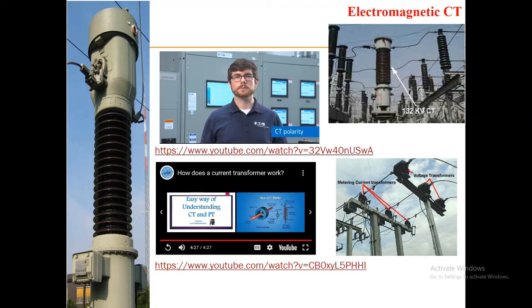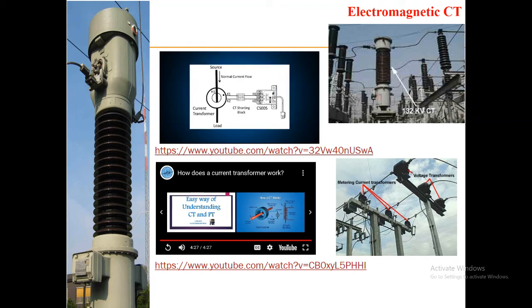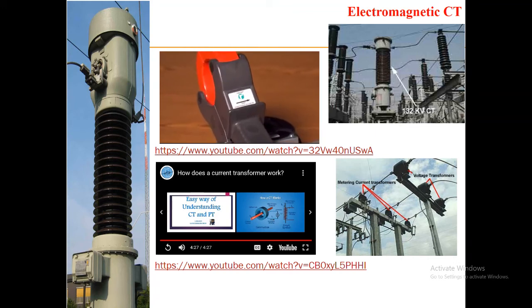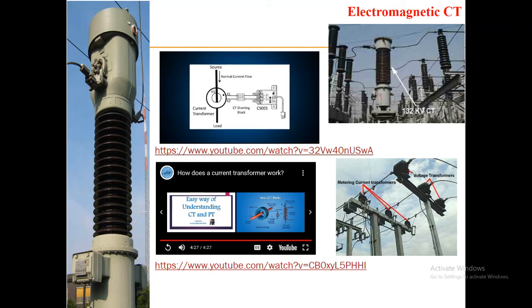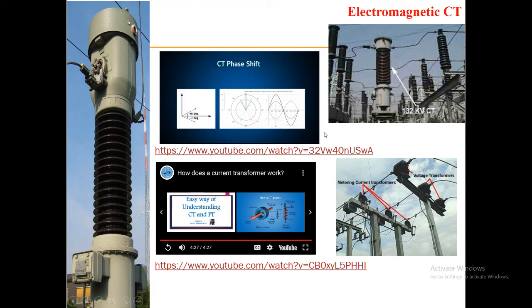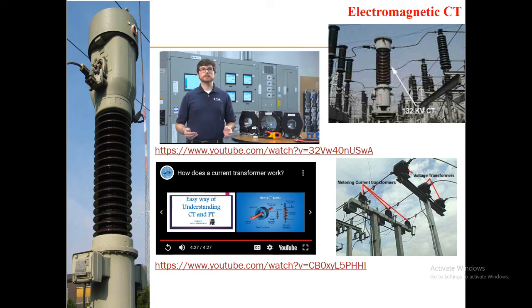In addition to CT saturation, the maximum frequency range that a CT can measure is typically 3 to 5 kilohertz. For most applications, this is okay since the harmonics on the power system are typically within this range. However, for high frequency applications like transients in the hundreds of kilohertz or megahertz range, special highly accurate CTs like these Pearson CTs can be used. CTs have polarity dots, arrows, or markings indicating current flow direction. The primary wire enters the CT on the side indicated by H1 or P1, and the load side is indicated by H2 or P2. When a CT has an arrow indicating direction, the arrow points towards the load. The current on the secondary comes out of X1 and returns on X2. A common problem when using CTs is that after installation, a negative power is measured. This can happen if the primary orientation or the secondary wiring is backwards or a setting is incorrect in the meter.